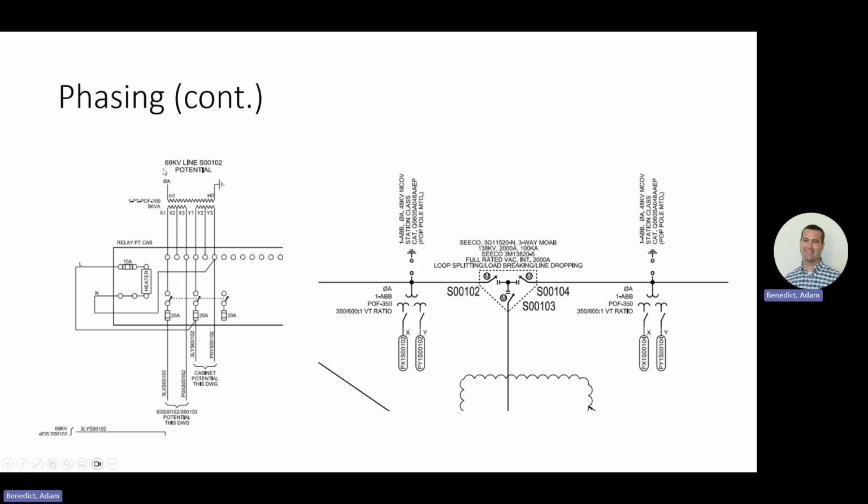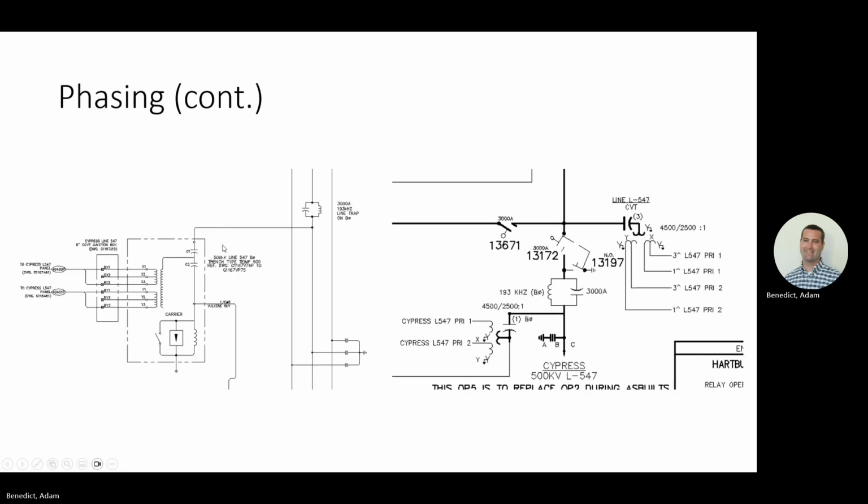They're very standardized and locked in on their practices. It's a very large utility, but for them, they're just going to put A, and we're making sure it matches A here, and then we're also looking on the EA as well to make sure that is A. But they're not going to show it actually connecting into the bus work. This is a different utility, and this is going to show more of the bus work.